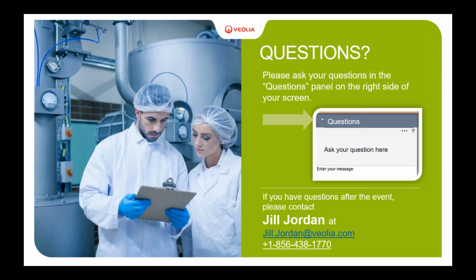Yes, Timur's just telling me we could also use turbidity to look at an extreme case of a lot of solids coming down in the process. But we've been using a total organic carbon meter to do this, and it's been working quite well at a number of our facilities now. That's how it works. It's very easy. Total organic carbon measurement in, calamity tank in, some software in your program, and it's all done.